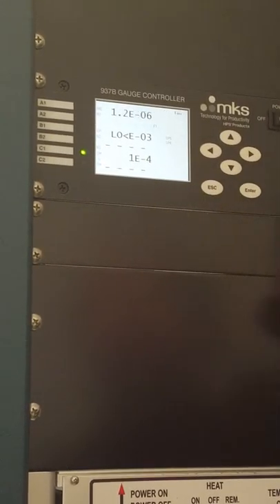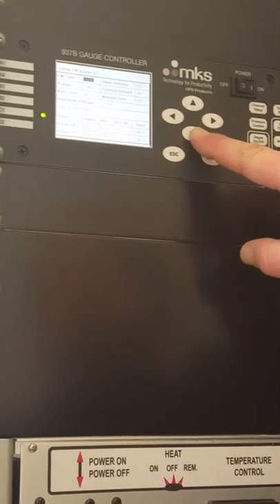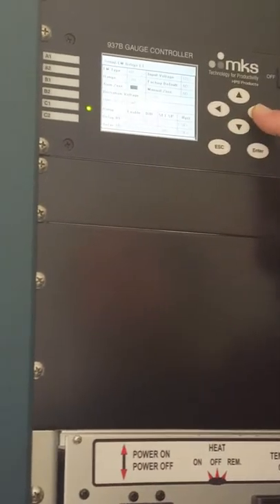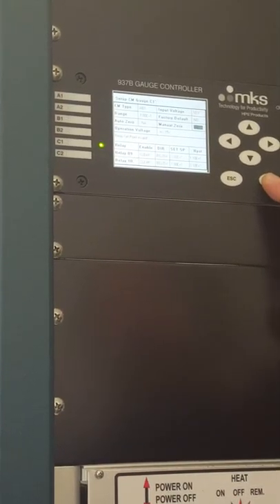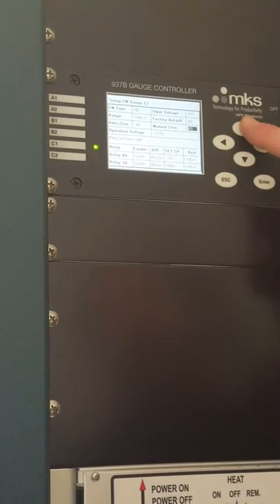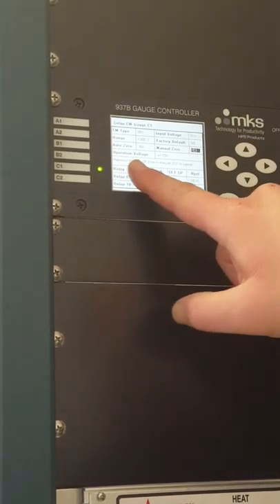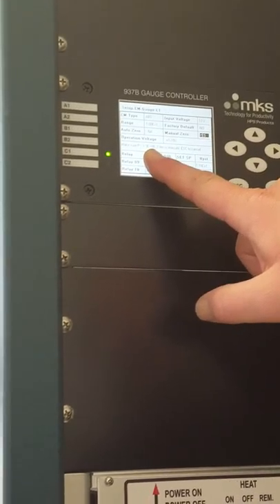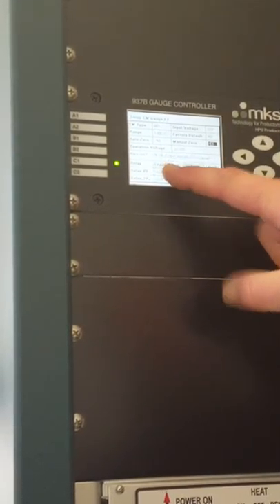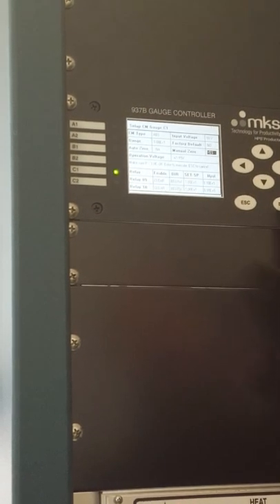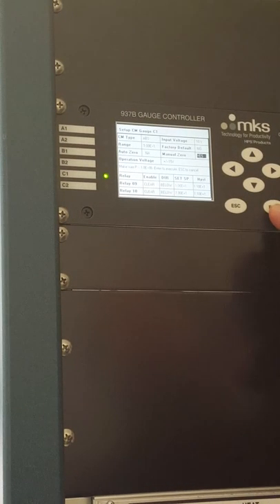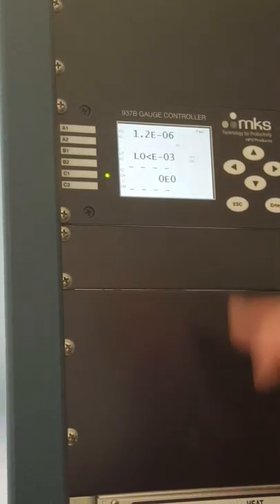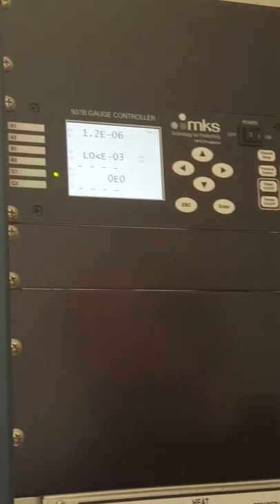Going through channel setup. We go down to manual zero. We change the no to a yes. It says, make sure your pressure is less than 1×10⁻⁶. Press enter to execute. I'm just going to go ahead and do it anyway here. Now it's zero.